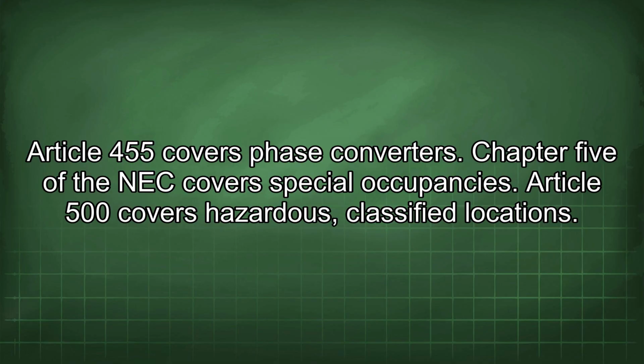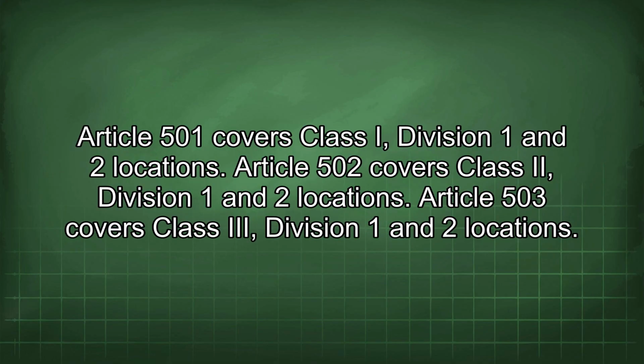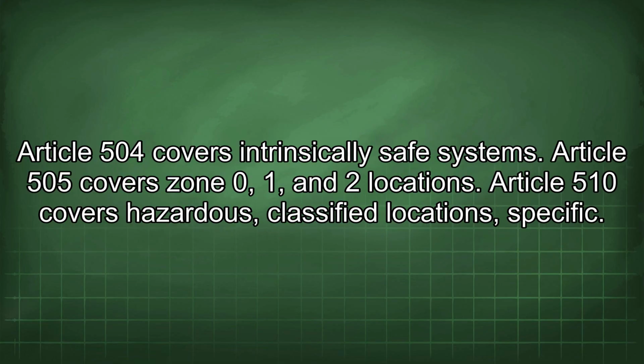Article 500 covers hazardous, classified locations. Article 501 covers Class I, Division 1 and 2 locations. Article 502 covers Class II, Division 1 and 2 locations. Article 503 covers Class III, Division 1 and 2 locations. Article 504 covers intrinsically safe systems. Article 505 covers Zone 0, 1, and 2 locations. Article 510 covers hazardous, classified locations, specific.